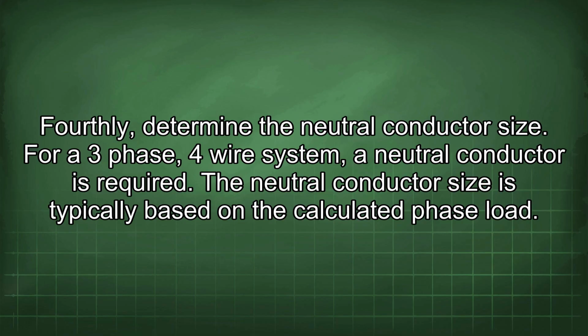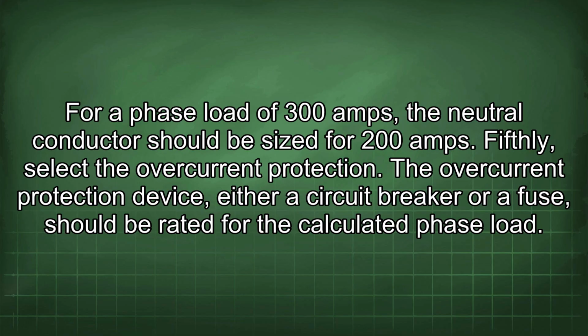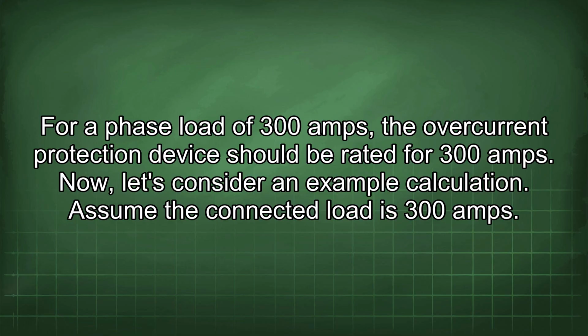Fourthly, determine the neutral conductor size. For a 3-phase, 4-wire system, a neutral conductor is required. The neutral conductor size is typically based on the calculated phase load. For a phase load of 300 amps, the neutral conductor should be sized for 200 amps. Fifthly, select the overcurrent protection. The overcurrent protection device, either a circuit breaker or a fuse, should be rated for the calculated phase load. For a phase load of 300 amps, the overcurrent protection device should be rated for 300 amps.